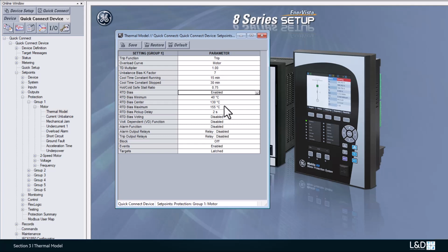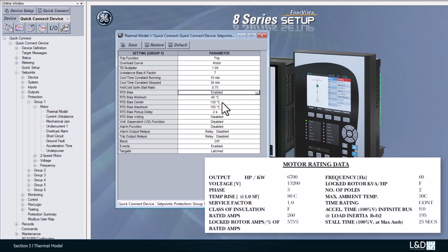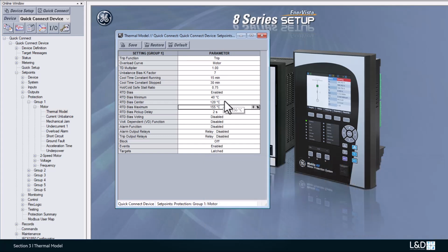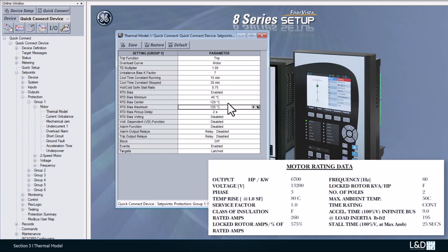The minimum temperature is set to 40 Celsius, which is the ambient temperature. And the center point is set to the motor's hot running temperature, calculated with the temperature rise of the stator plus ambient temperature. The temperature rise of the stator is 80 degrees. Therefore, the RTD center temperature, we can set this to 120 Celsius. And RTD bias maximum set point is set to the rating of the insulation or slightly less. For the class F insulation used in this motor, which is rated at 155.